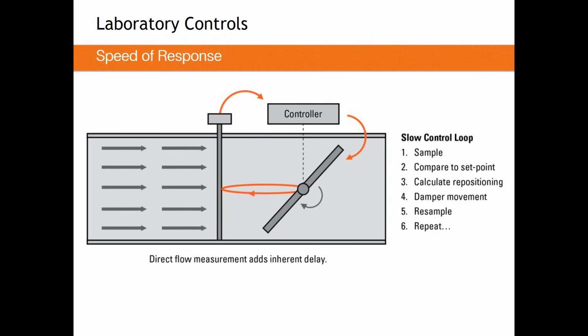So this is where you shouldn't ever get caught up in the language used when talking about these speeds of response. It's important to compare the devices. In some aspects, a Venturi valve can be faster than a high accuracy terminal, but the most important thing here is if we do care about speed, we need to define the speed. If you need a device that controls or accommodates a change in duct static pressure instantly, you need to define that and then select a Venturi valve.